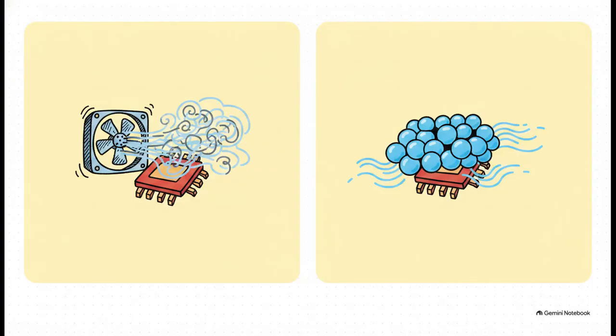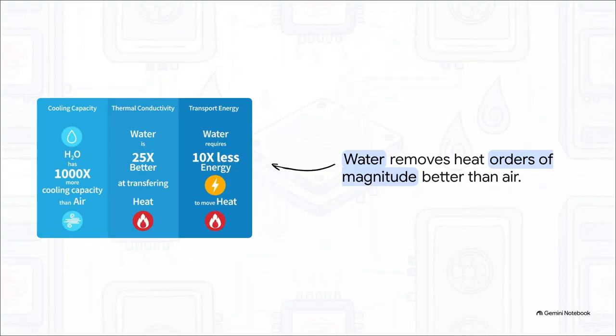It all comes down to the fundamental difference between how air and liquid actually work. Air cooling essentially relies on brute force, massive, super energy-hungry fans blowing desperately over hot chips. But liquid utilizes completely different physical properties. Because the molecules in liquid are packed so much closer together than in air, liquid is highly conductive. It's just inherently scientifically better at transferring heat away from a source. And we're not talking about a slight improvement here. Liquid is orders of magnitude better.